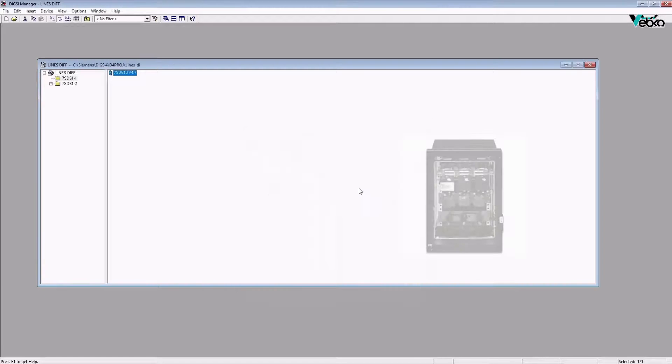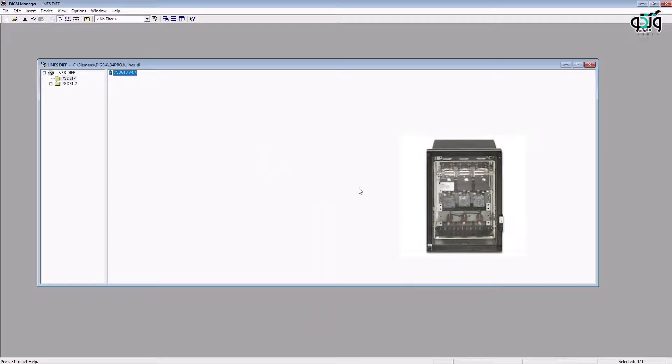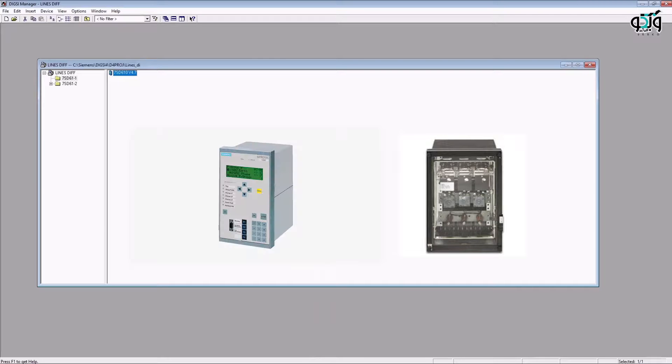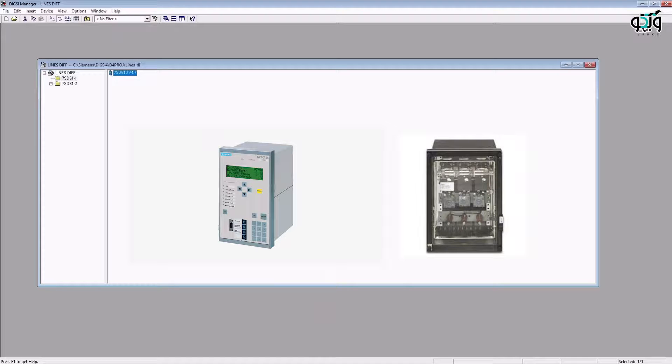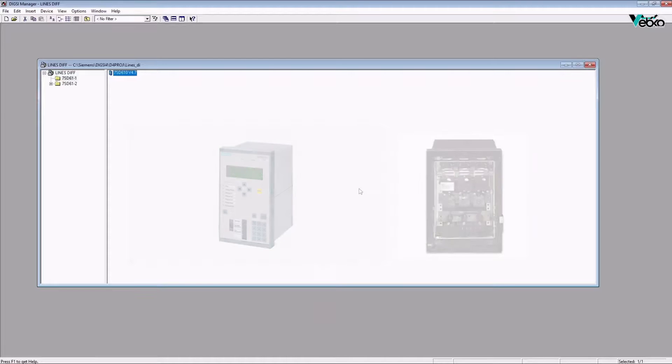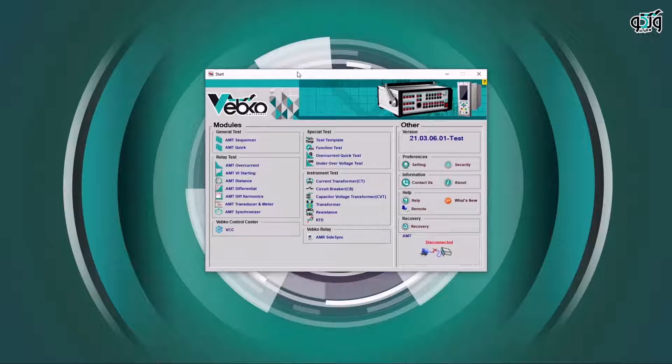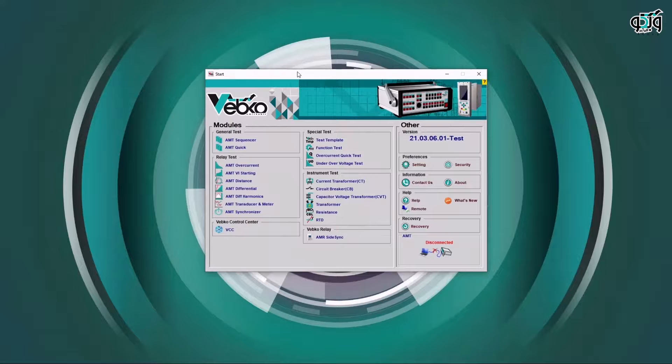Old longitudinal differential relays use the ratio of differential current to restrain current and if this ratio was higher than the specified settings, the trip was issued while the modern differential protective relays, a characteristic named alpha plane is used. In this design, the vector ratio of remote current to local for every current phase and negative and zero-sequence currents are used. Here, to better present the end-to-end test method, a longitudinal differential protective test is performed on 7SD610 relays of Siemens company.